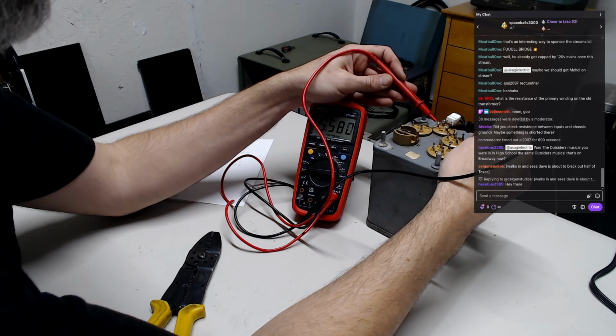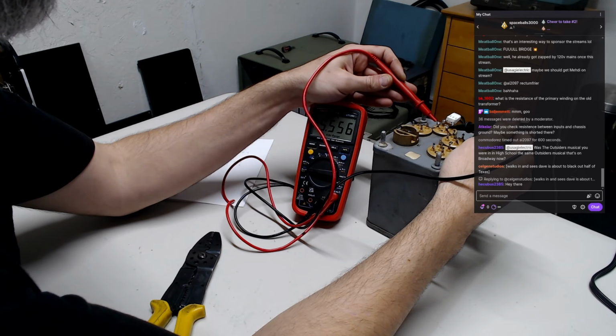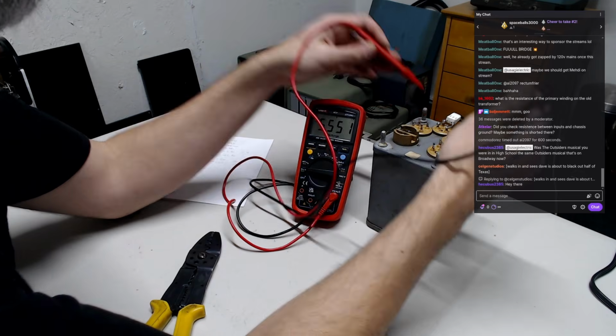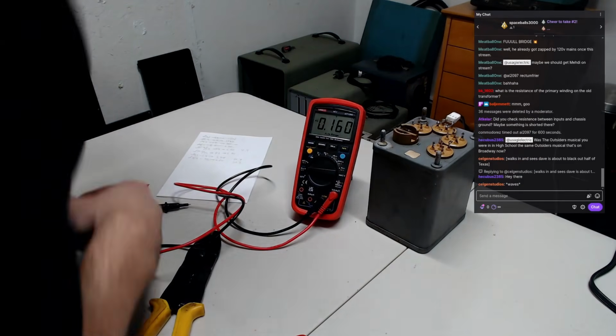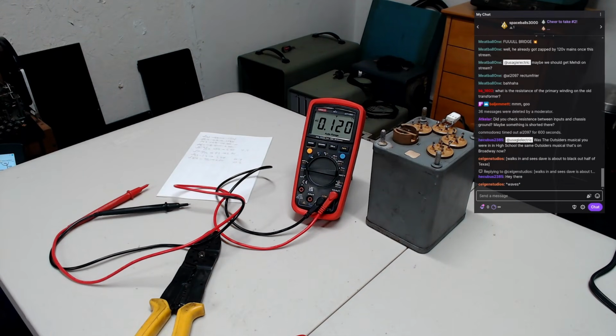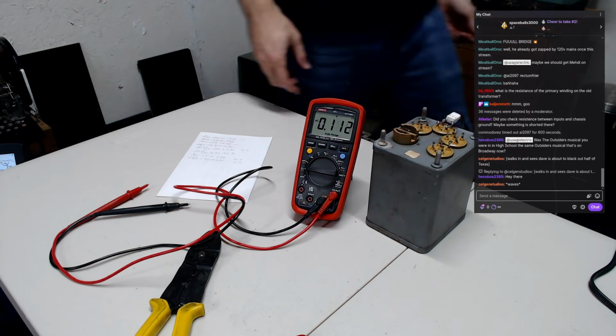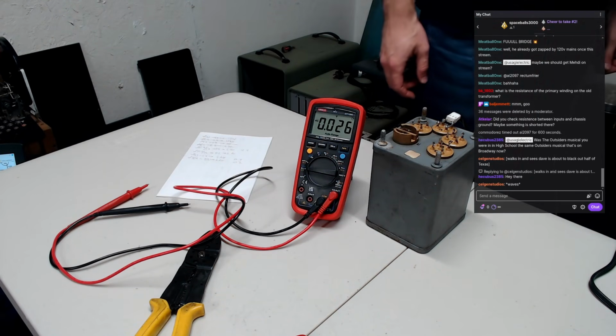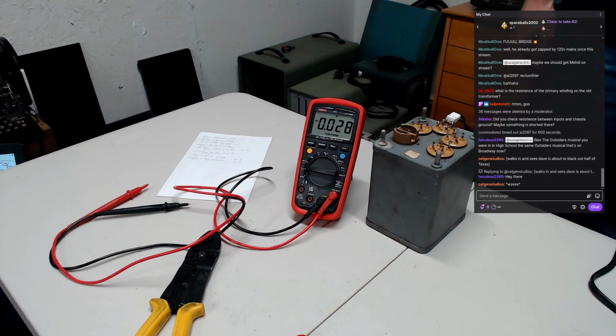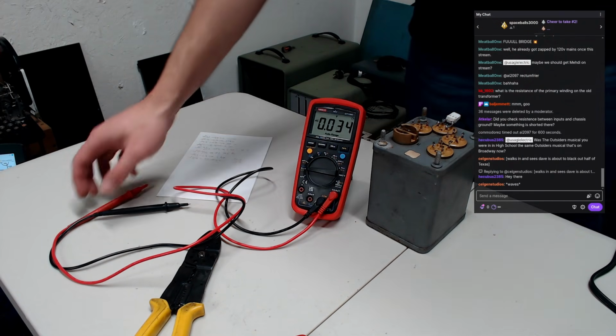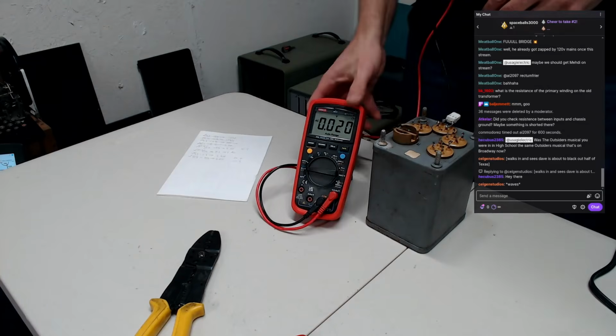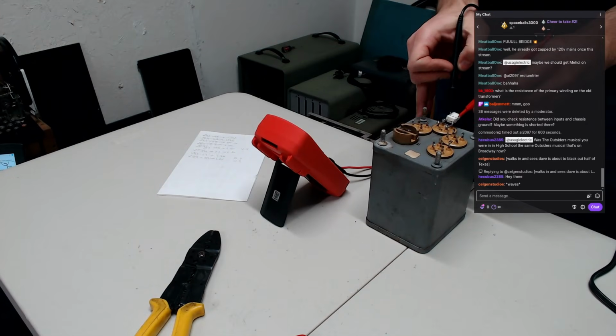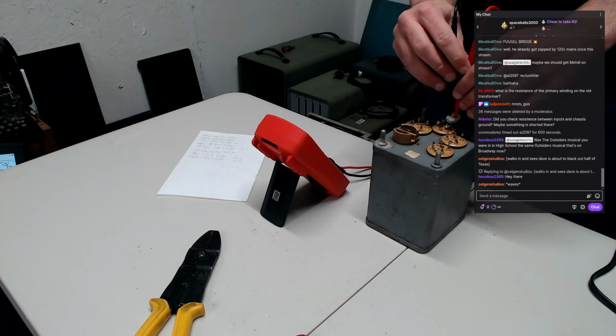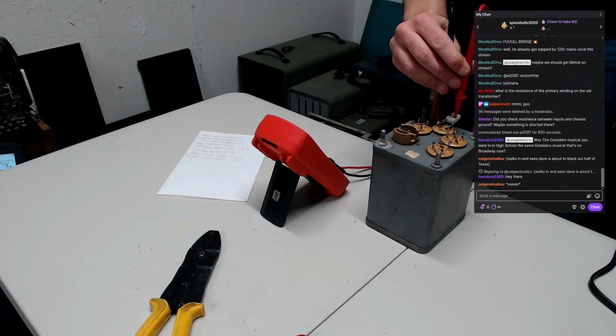No, I've got mains of 5.5 volts. That doesn't seem right. I didn't pop a breaker or anything. Why would mains be so low? Because it's being pulled low by a heavy load. If you've got a shorted secondary, wouldn't that be a heavy load? Yeah, I could see that.